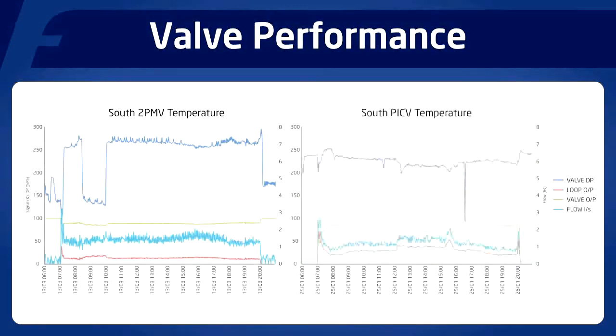If we show the flow through the pressure independent control valve on the south air handling unit compared to the same air handling unit on a different day but with similar outside temperatures when fitted with a conventional valve, it is noted that the flow through the pressure independent control valve is significantly lower and more stable than the flow through the two-port modulating valve.